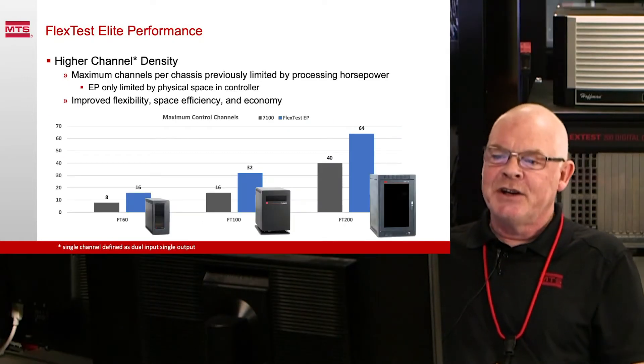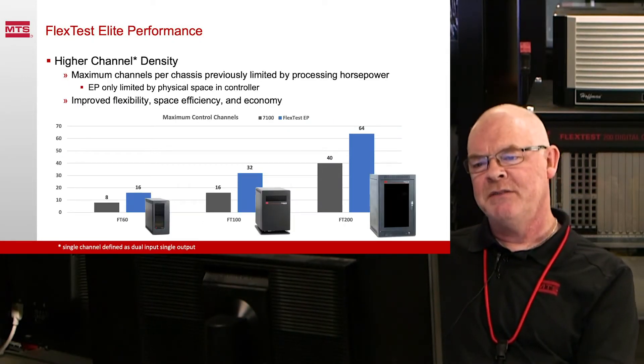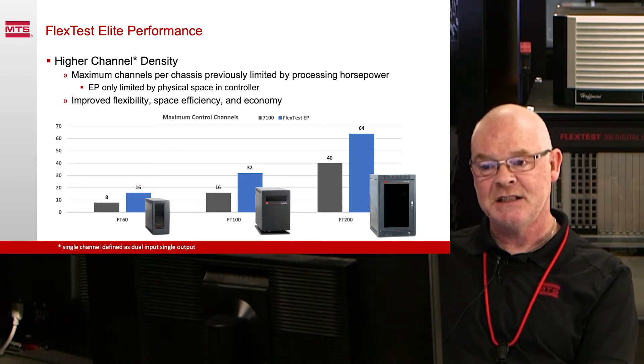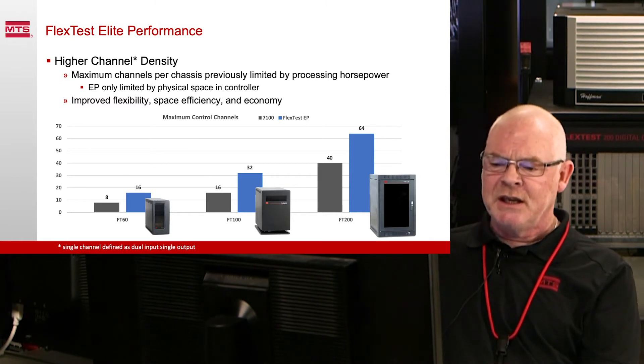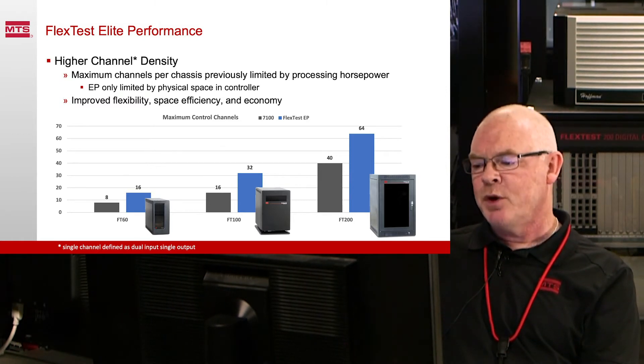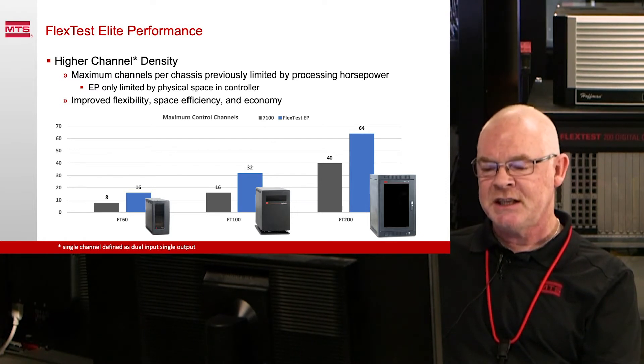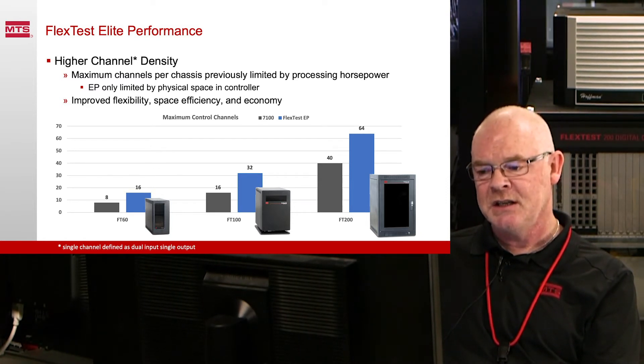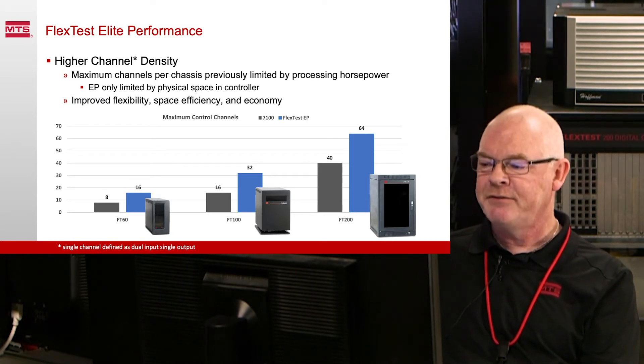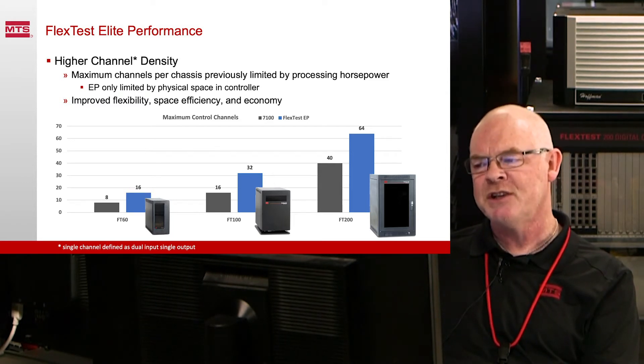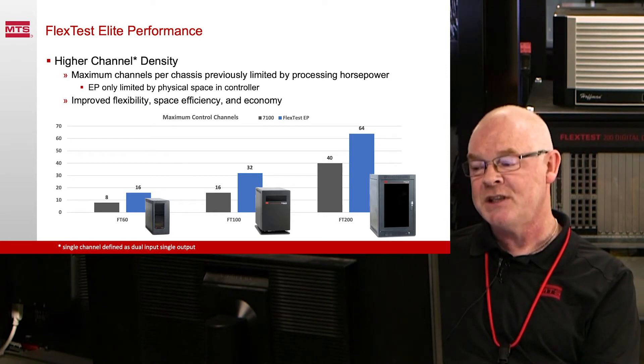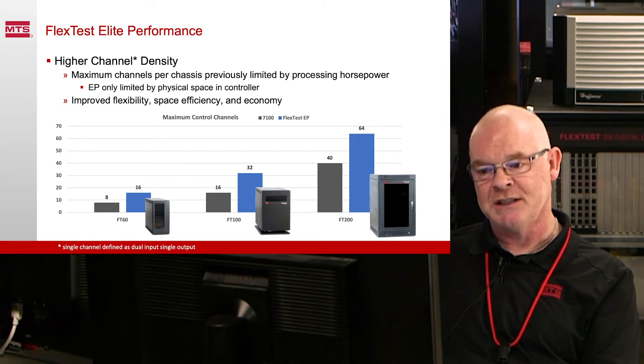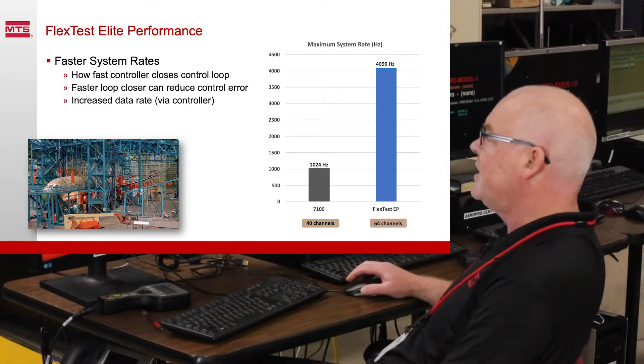The next slide looks at how we can achieve higher density of control channels inside the chassis with the Elite Performance. Here you can see we have the FT60, the FT100, and the FT200. In the FT60 we can double the channel capacity to 16; in the FT100 we can double the capacity to 32; and in the FT200 we can increase it to 64 — limited only by the available real estate inside the 20-slot chassis.